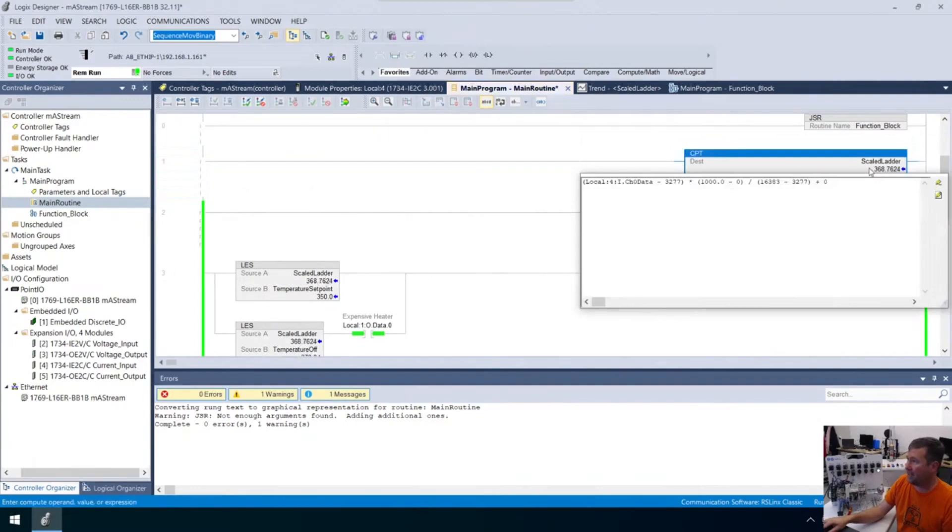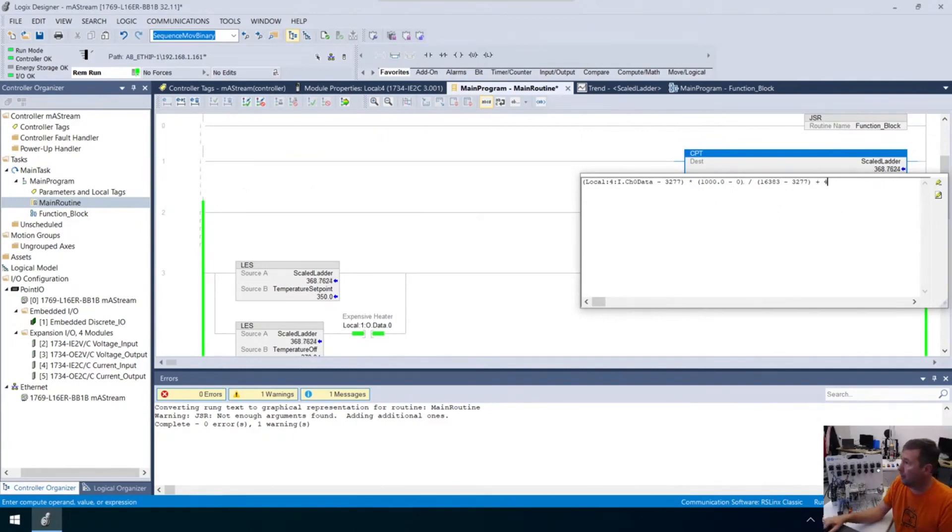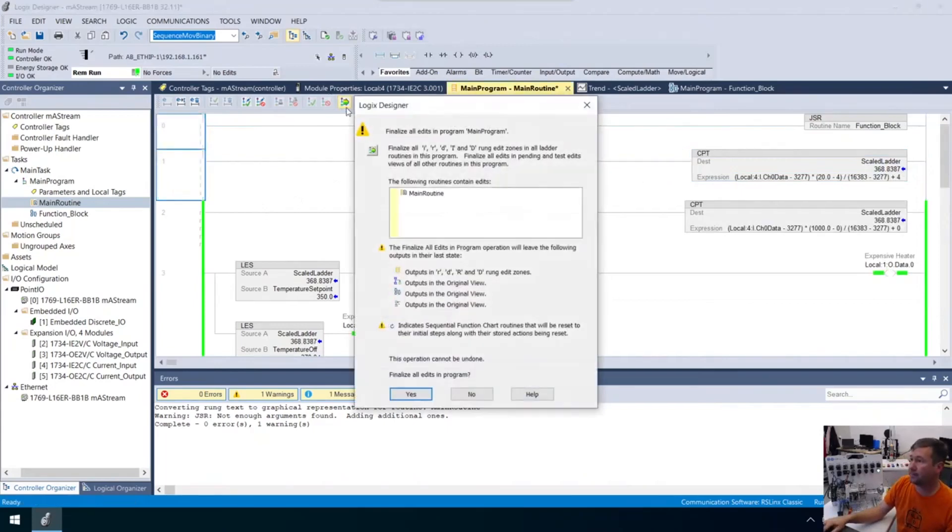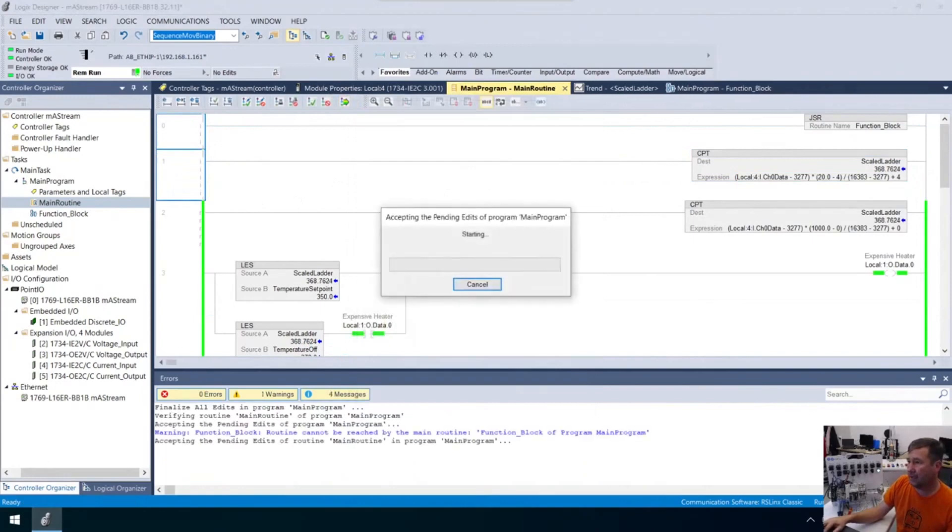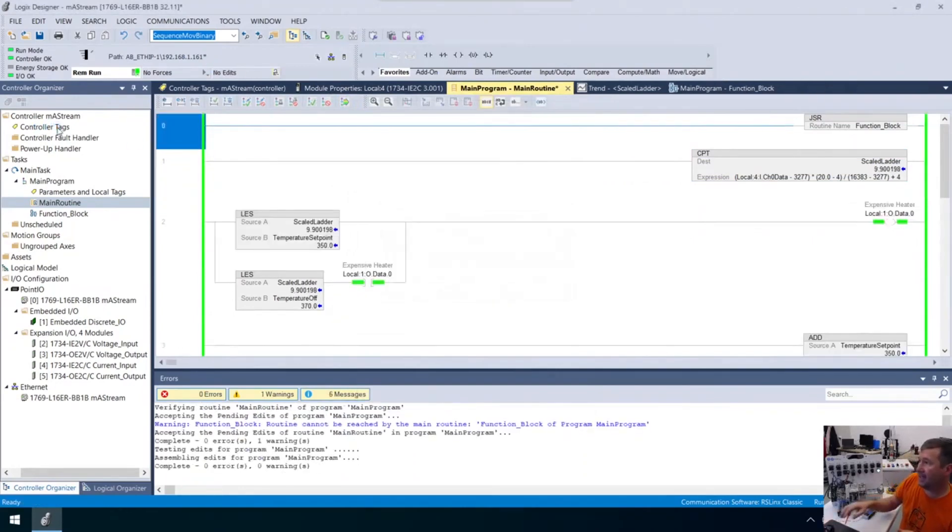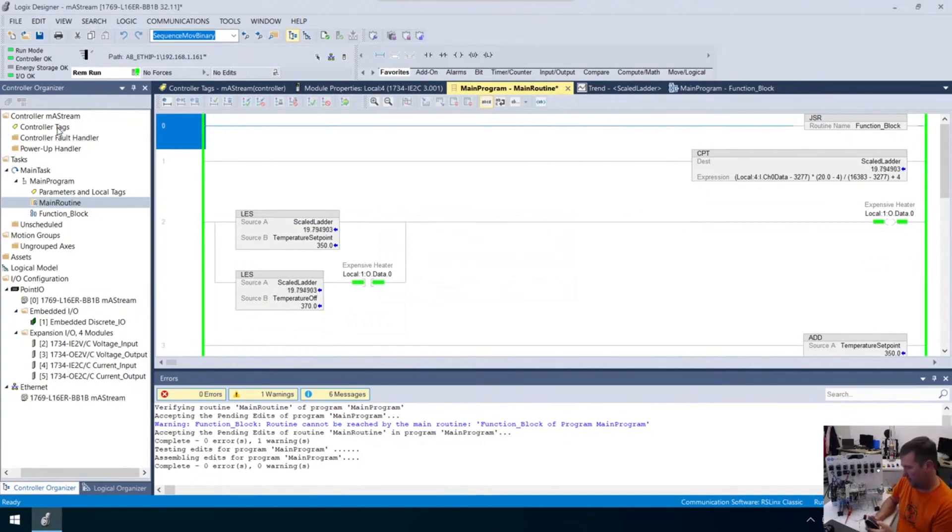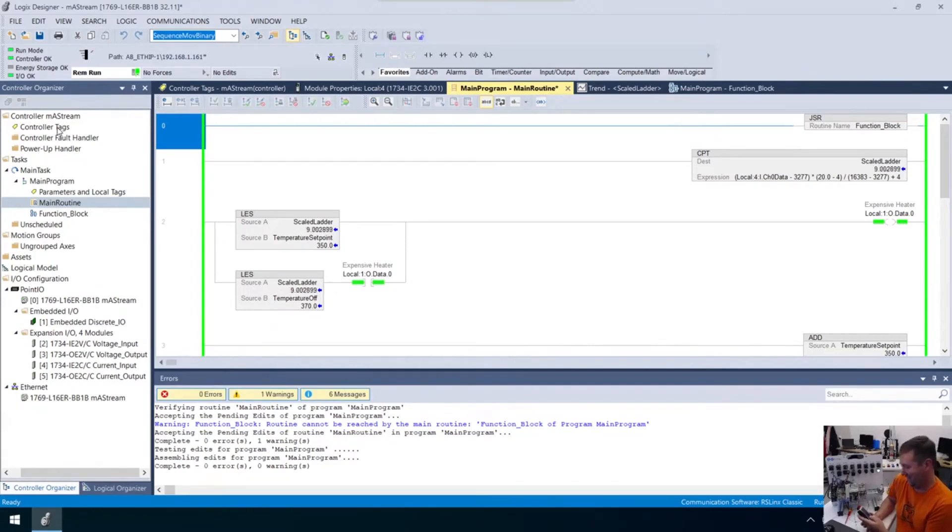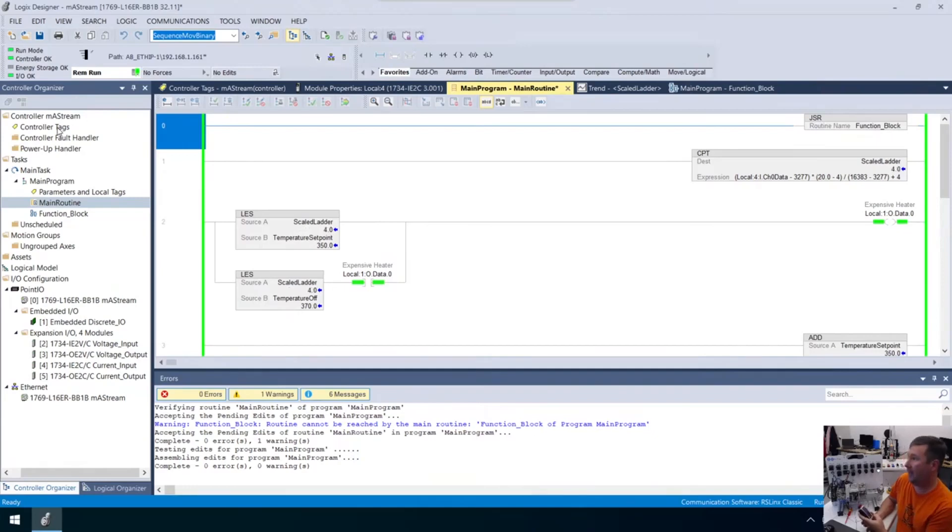I'm actually going to change our values back to four and 20. We're going to have four here and this will be 20, putting us back at our four to 20 milliamp scaling. Let me test that. I go up to 20 milliamp and that gives us 20. I go down to four and we're showing four milliamp. That's back like it was.